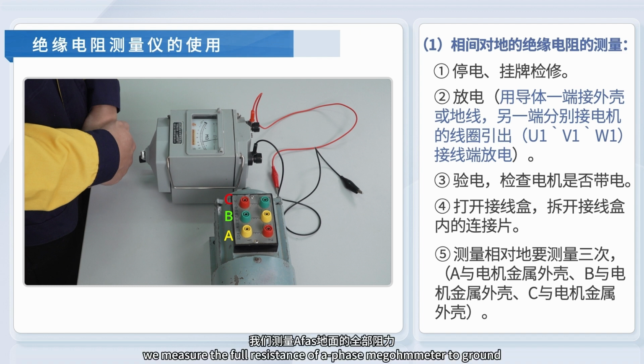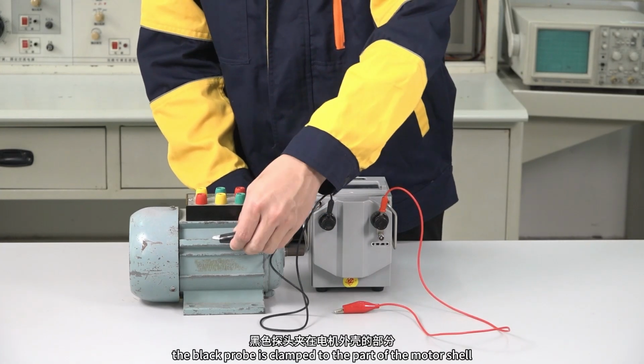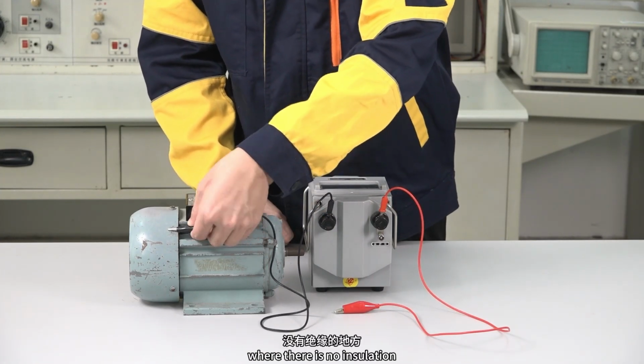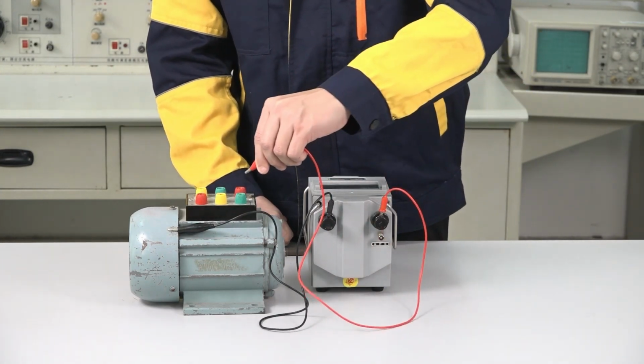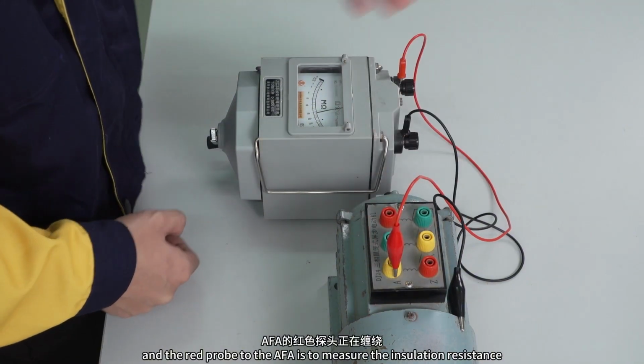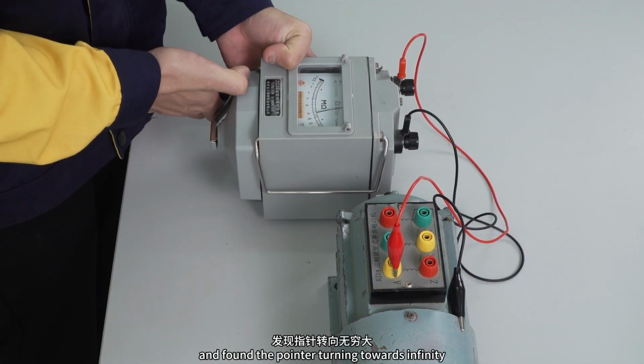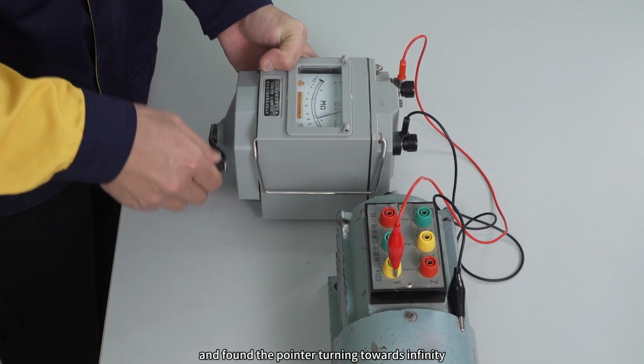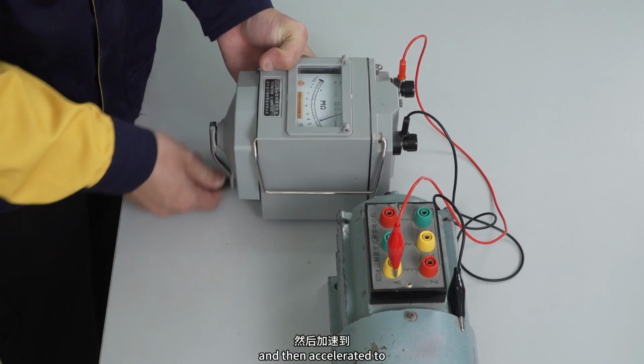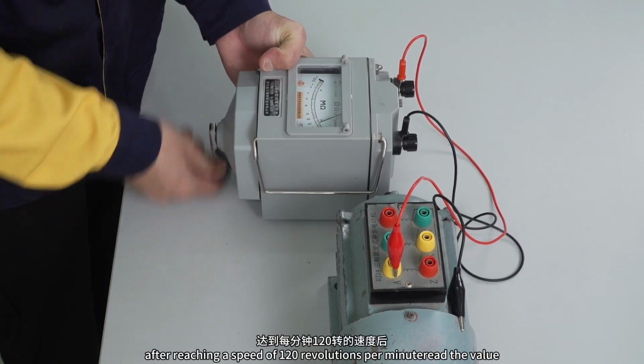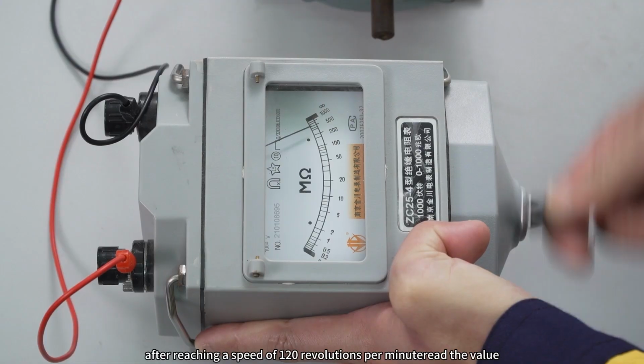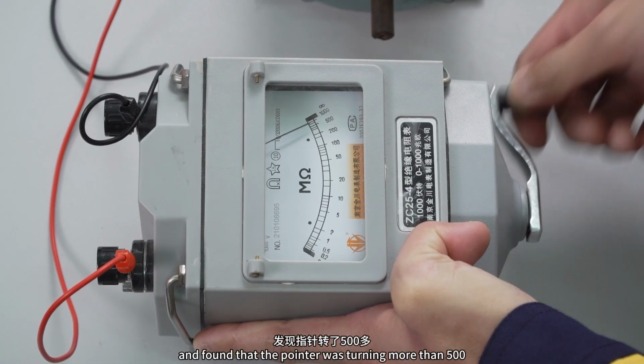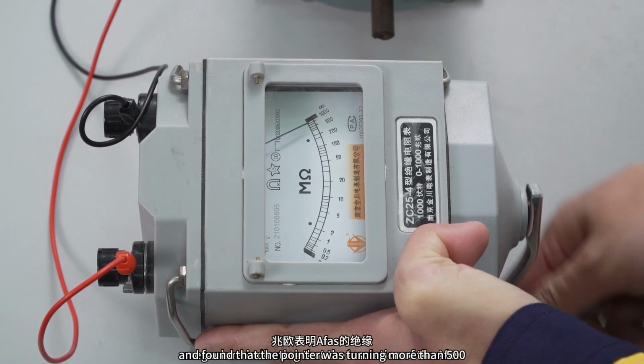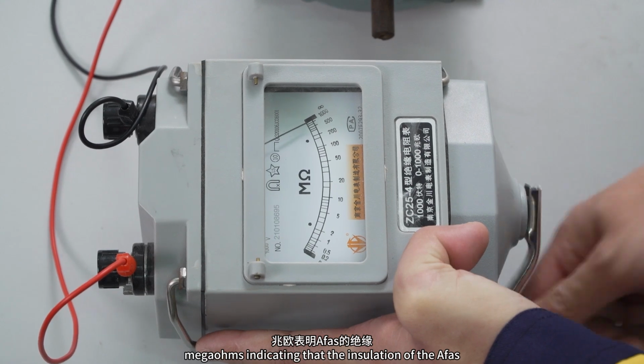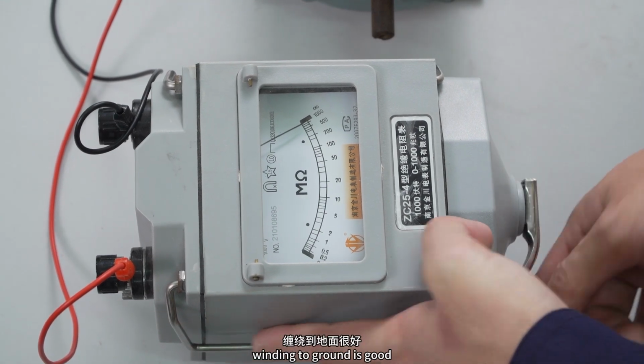We measure the insulation resistance of A phase to ground with the megohmmeter. When measuring, the black probe is clamped to the part of the motor shell where there is no insulation, and the red probe to the A phase to measure the insulation resistance. The pointer turns towards infinity, and then we accelerate. After reaching a speed of 120 revolutions per minute, read the value, and the pointer turns to more than 500 megohms, indicating that the insulation of the A phase winding to ground is good.